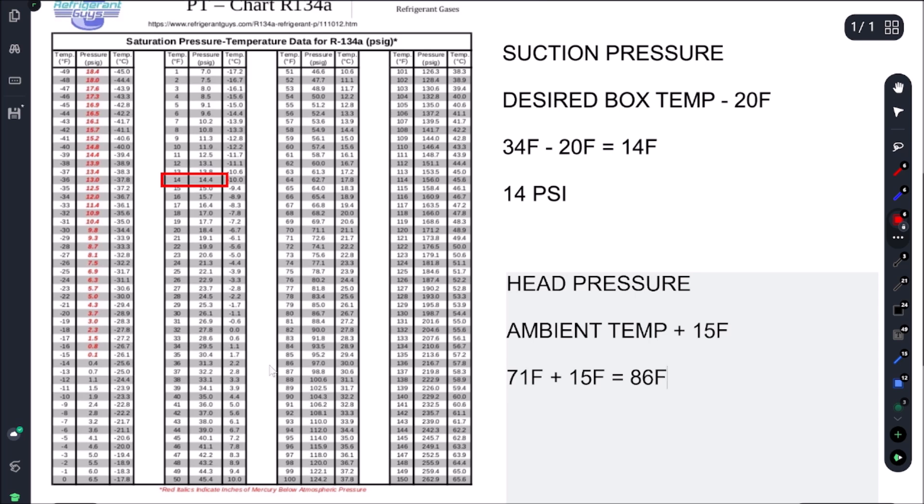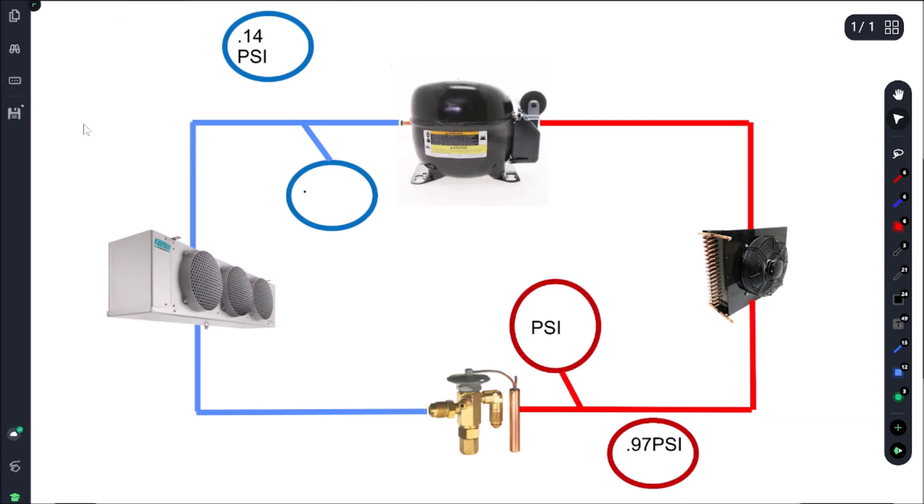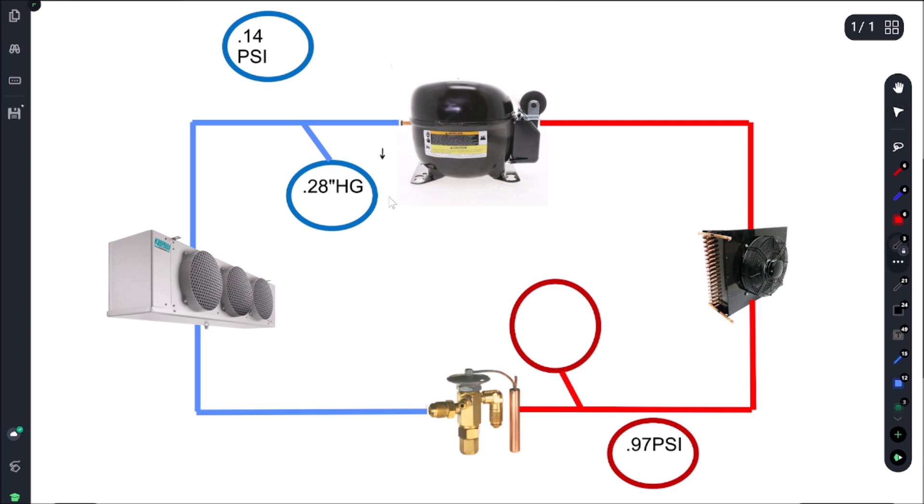All right, so let's head over to our refrigeration cycle chart. We're looking for 14 PSI and 97 PSI and as you can see, we're in a vacuum. We're getting 28 inches mercury and then on our high side we were getting 97 PSI. So that means we're low on our suction, we're low on our head pressure. That means we either have a restriction at our metering device, in this case we have a cap tube, or we are low on charge.